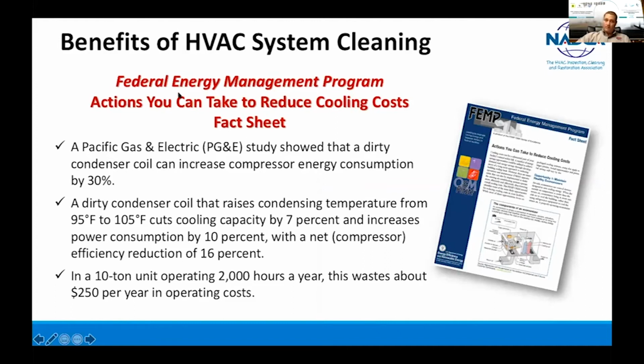So, just more benefits of cleaning HVAC systems. A Pacific Gas and Electric PG&E study shows that a dirty condenser coil can increase compressor energy consumption by 30%. A dirty condenser coil that raises condensing temperatures from 95 degrees Fahrenheit to 105 degrees Fahrenheit cuts cooling capacity by 7% and increases power consumption by 10% with a net efficiency reduction of 16%.